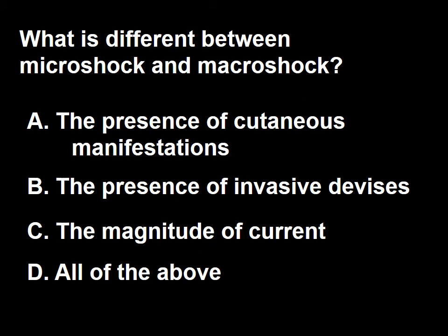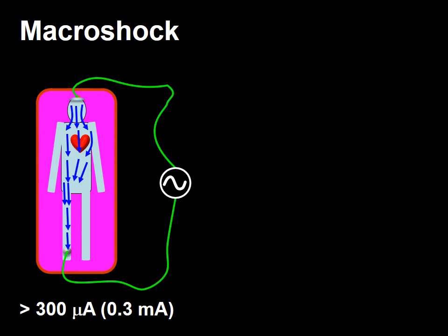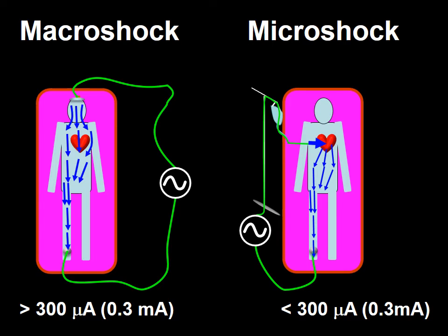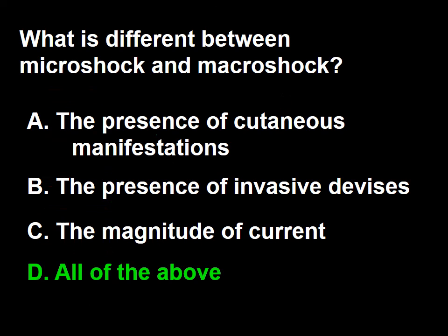Next question: what is different between microshock and macroshock? A: the presence of cutaneous manifestation, B: the presence of invasive devices, C: the magnitude of the current, D: all of the above. A macroshock is the clinical consequence of a large externally applied current — the magnitude of the current is above the perception threshold. A microshock is defined as a small quantity of electricity not large enough to be perceived if applied to the skin, but capable of producing ventricular fibrillation if applied to the skin in patients with internal devices close to the heart, or if applied directly to an internal device. The answer to this question is D.